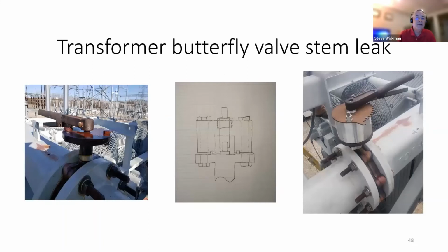for this customer. Here's one of the situations where a utility customer had just regasketed this transformer. This is like a 345 to 138 transformer in a transmission substation that they had just finished regasketing when they were about to put it back in service. It was July summertime. The operations folks were crying about getting this unit back, and as opposed to taking this thing out and replacing this butterfly valve, they called on us to come up with a solution. Oil was working its way up through the valve stem here, and our guys came up with this design to effectively contain that leak. And you can see that cylindrical clamp in place on that butterfly valve operating handle in the picture on the right, effectively containing that leak.